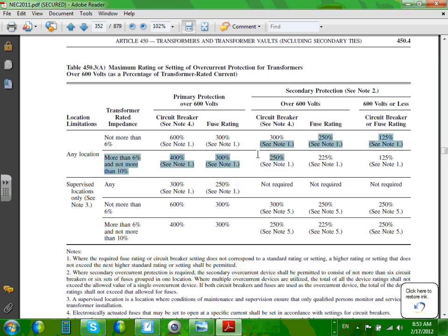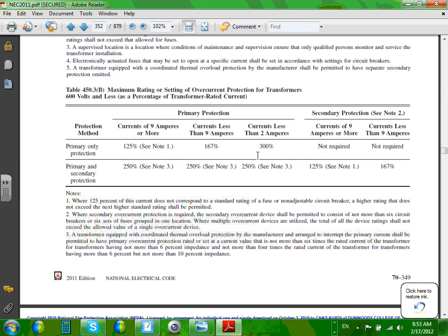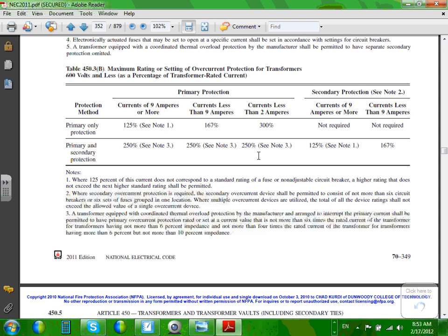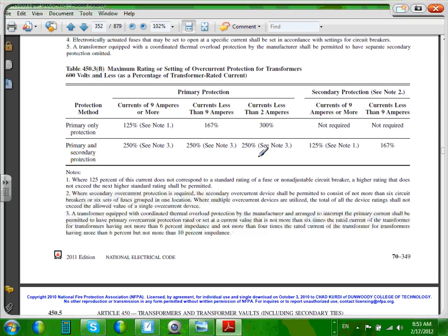So what the author did, they grabbed this table, and this is for if the voltage, the primary or secondary, is over 600 volt. If both the primary and the secondary are less than 600 volt, then you use this table, and you're going to default to primary, secondary protection. Just default to this one. Most likely current of 9 amp or more. So this is your default. Most likely secondary protection.